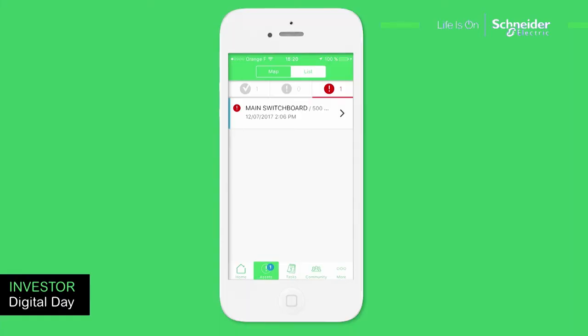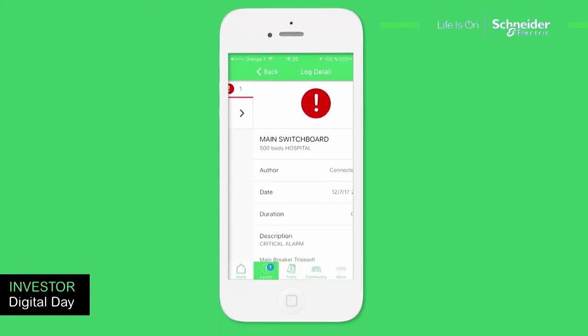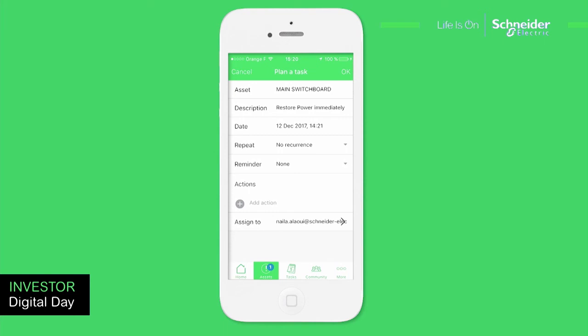Oh, I just got paged. I've just received a critical alarm stating that the main breaker has tripped. Fortunately, thanks to our ATS switch, all the generators have started properly and all the critical loads are correctly powered. However, still 80% of the non-critical loads are unpowered, so I need to assign these critical alarms to my field technicians for immediate repair.